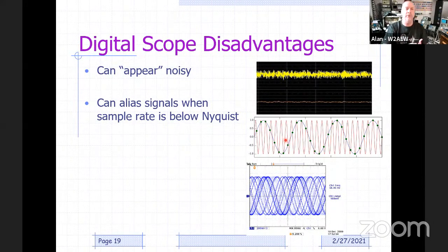I know you're doing all CW, but you have to dial down to maybe a millisecond per division or 500 microseconds per division. And by doing that, the sample rate of the stored waveform may come down to where it's going to be lower than the RF carrier, and you're going to alias the signal. Okay, so that's something to be thoughtful of if your application is going to be monitoring your RF envelope.